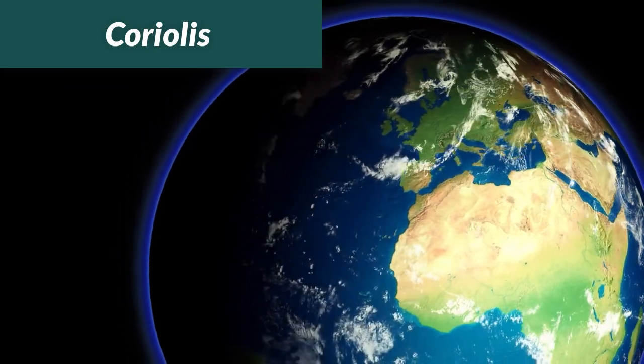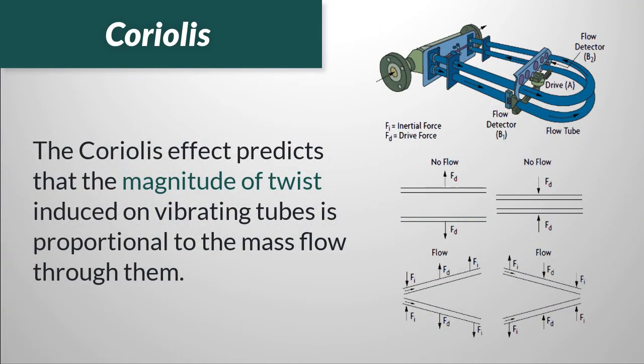When mass flows through a vibrating tube, Coriolis forces will tend to twist the tubing. By measuring the magnitude of displacement caused by this twisting force, the Coriolis meter can directly calculate mass flow rate.